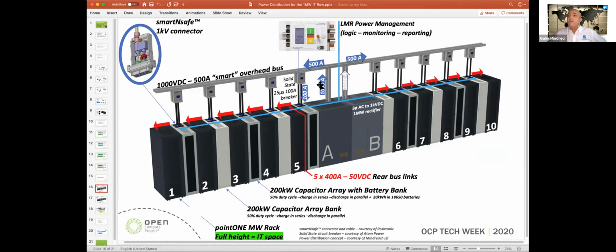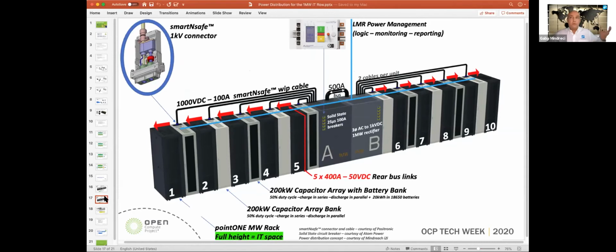And the reason this rectifier switchgear is placed in the center of the row is because this will simplify the bus distribution on each side with 500 amps going in each side. So 500 amps going in this portion, 400 in this portion, 300, 200, 100 to the last rack. And this is achievable with an overhead bus system, such as this one shown in this configuration. And this overhead bus is a smart, holistic type system that could also be replaced with a whip wire configuration, just like what we used to.